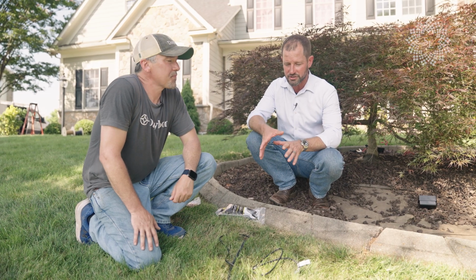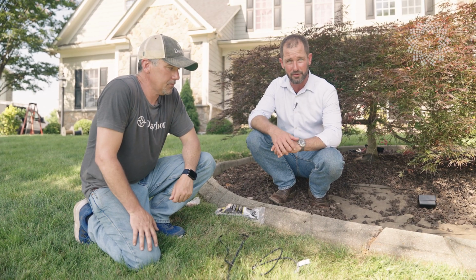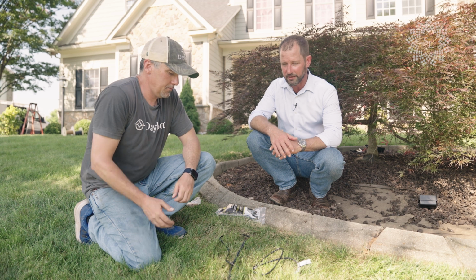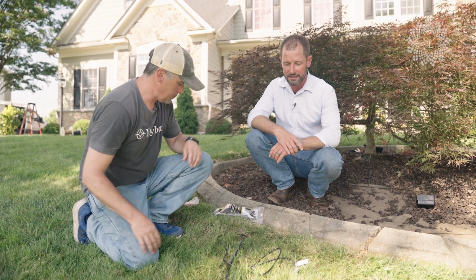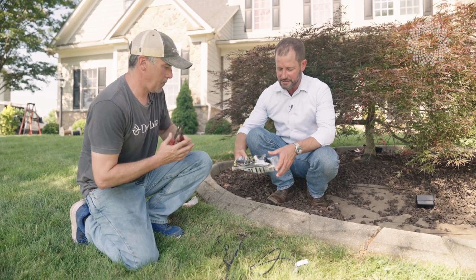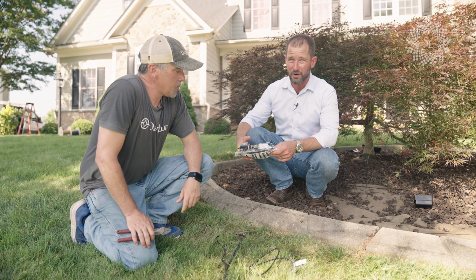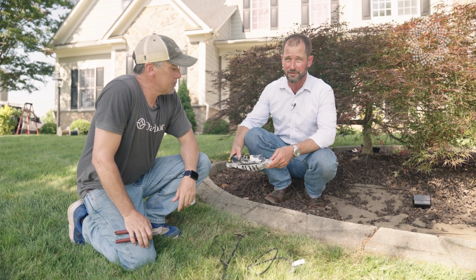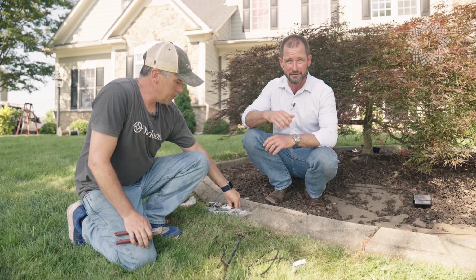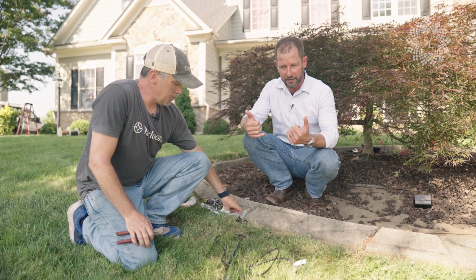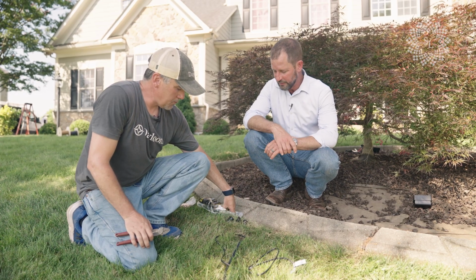Josh is going to show you this connection style, how we do it and why we designed it this way. This is UL listed without the copper tube, but we add the copper tube because it makes sense to get the connection really tight and permanent, and then pull the connections away from each other.